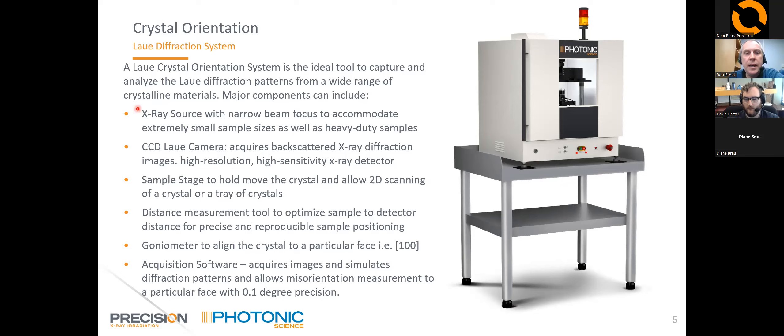The system comes with software to acquire images and a pattern simulator, and it allows misorientation measurements to a particular face with 0.1 degree precision.